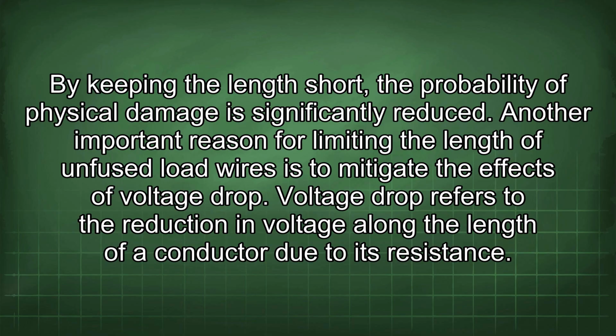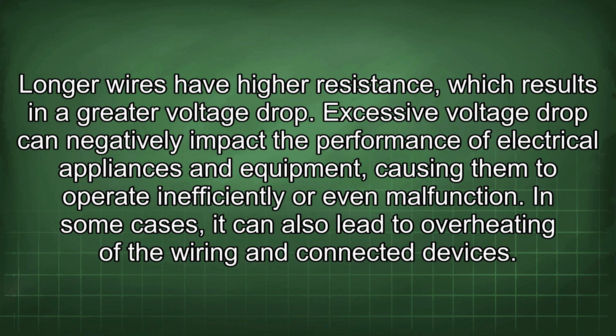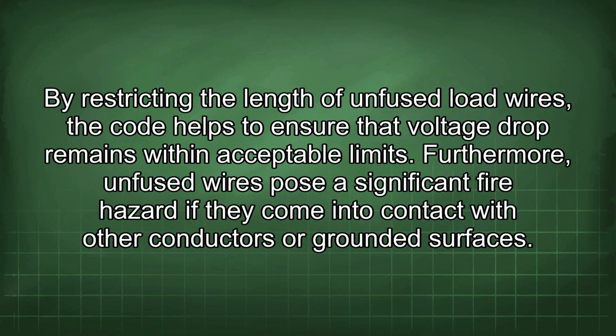Another important reason for limiting the length of unfused load wires is to mitigate the effects of voltage drop. Voltage drop refers to the reduction in voltage along the length of a conductor due to its resistance. Longer wires have higher resistance, which results in a greater voltage drop. Excessive voltage drop can negatively impact the performance of electrical appliances and equipment, causing them to operate inefficiently or even malfunction. In some cases, it can also lead to overheating of the wiring and connected devices. By restricting the length of unfused load wires, the code helps to ensure that voltage drop remains within acceptable limits.